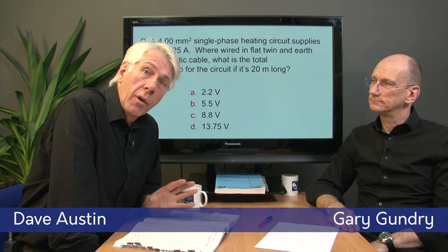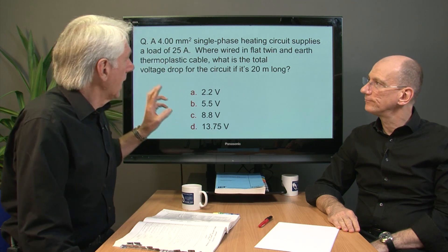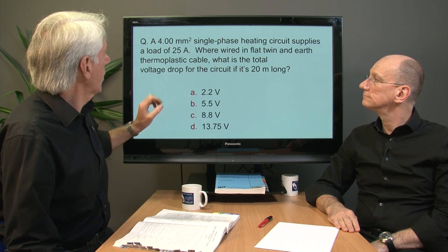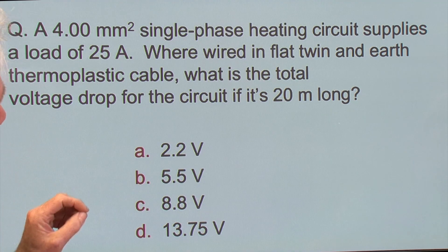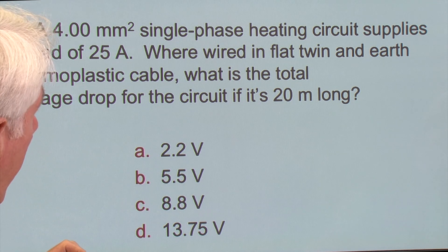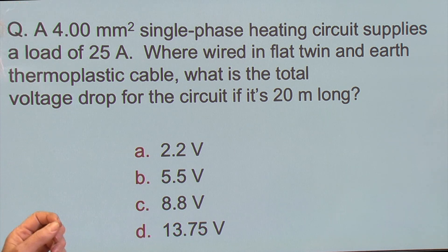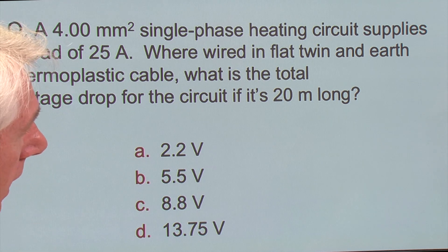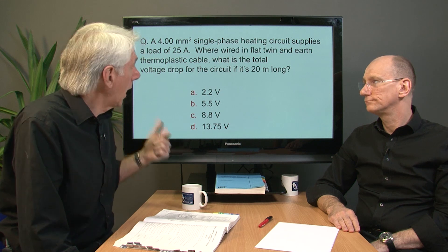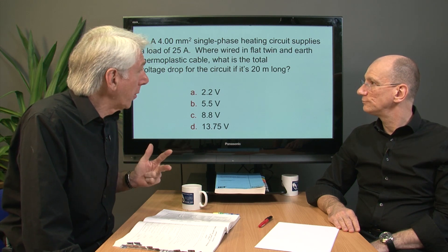Let's take a look at another question that involves voltage drop, but the difference between this one and the one we looked at previously in the series is we aren't given the voltage drop for the cable in the question. A 4mm² single phase heating circuit supplies a load of 25 amps, wired in flat twin and earth thermoplastic cable. What's the total voltage drop for the circuit if it's 20 metres long? So we've got the IB, the load current, and we've got the 20 metres, but we haven't got the all-important mV per ampere per metre.